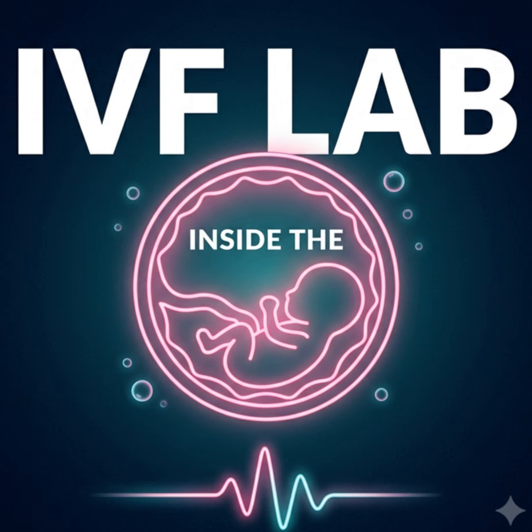Which is precisely why clinical micromanipulation required a fundamental redesign of optical physics. They had to completely abandon the traditional upright model and adopt what is known as the inverted microscope design. Now, the term inverted implies a simple flip, but structurally, we're talking about redesigning the entire optical axis, aren't we? Oh, it's a massive shift. We are dissecting the microscope and reversing its vertical orientation entirely. In the inverted architecture, the light source, the condenser, the phase contrast rings, all the things that deliver and shape the light, those are mounted high above the workbench, shining downward onto the sample. Okay, so the light is on top.